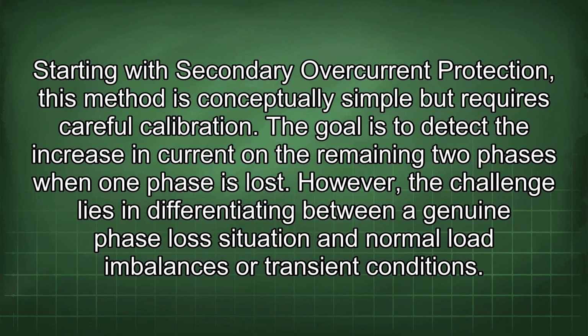Starting with secondary overcurrent protection, this method is conceptually simple but requires careful calibration. The goal is to detect the increase in current on the remaining two phases when one phase is lost. However, the challenge lies in differentiating between a genuine phase loss situation and normal load imbalances or transient conditions.